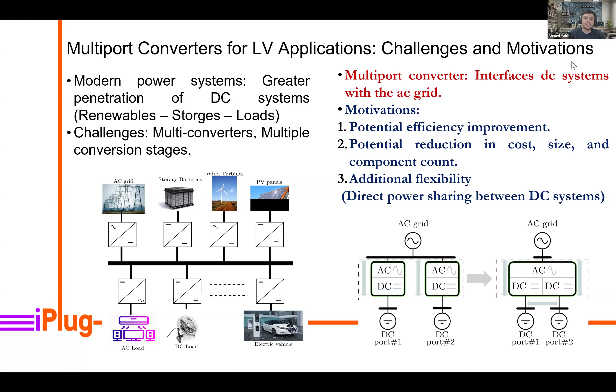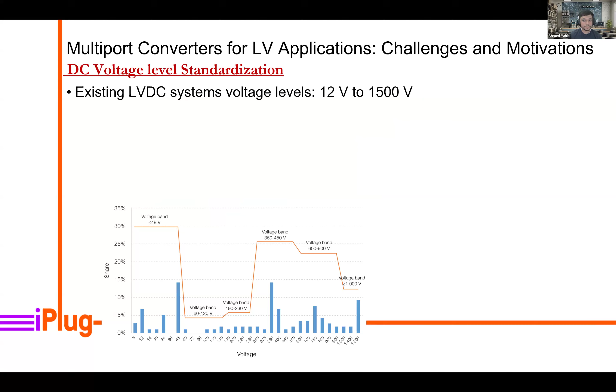So for our low voltage scenario, the first challenge we have faced is the standardization of the DC voltage level. We still don't have a specific standard for voltage levels. For DC voltage levels, you can see the levels spanning from 12 volt to 1.5 kilovolt for low voltage. And this not only affects the selection of passive and semiconductor devices, but also the selection of the topology itself. If we are talking about the European grid, if you're going to interface a system higher than 566, you need a boost type rectifier, like the voltage source converter.